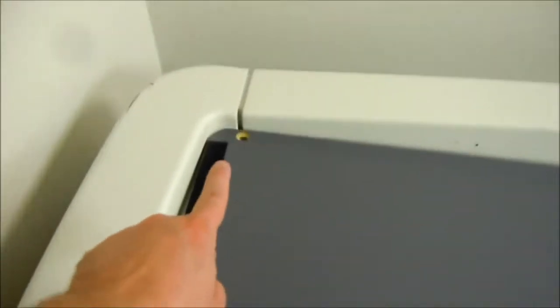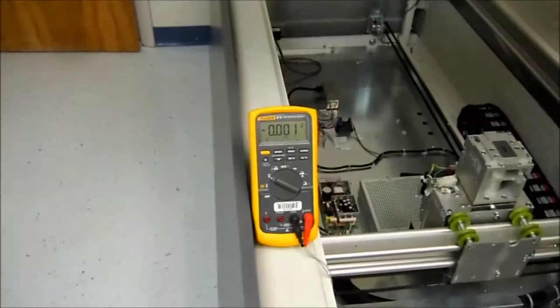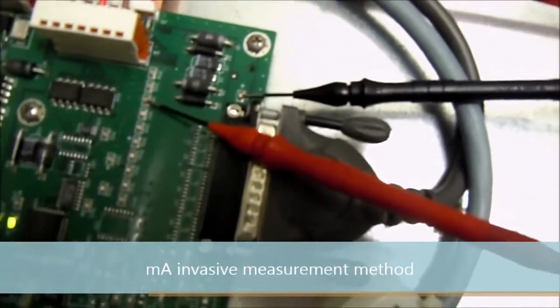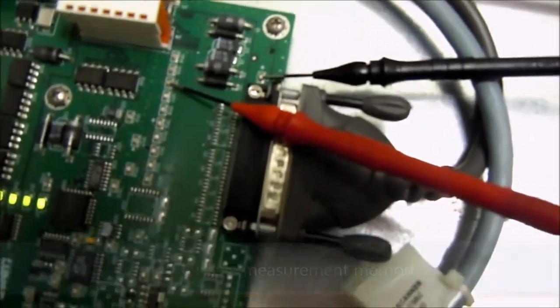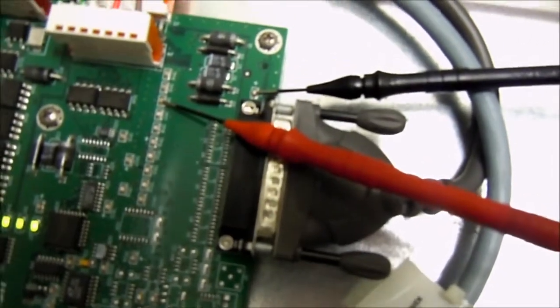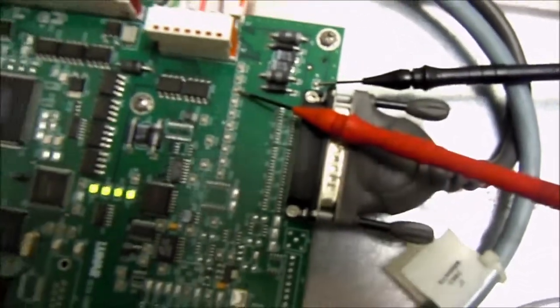mA verification. We're going to remove the table top, the four screws here, one, two, three, four. Here we're measuring the mA and we have the table off. We have our leads connected to test point one negative and test point 16 on the CSCB board.